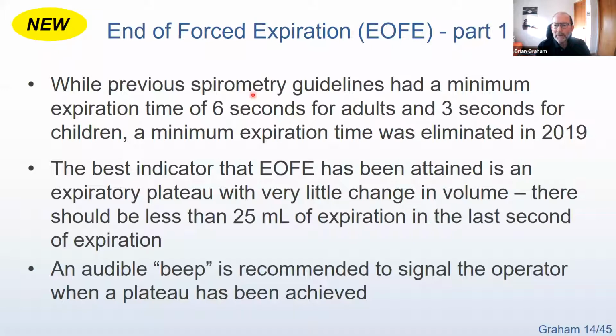So previous spirometry guidelines said you had a minimum expiration time of 6 seconds for adults, 3 seconds for children, and that's been eliminated in the new guidelines. We don't need that anymore. And there's good evidence to show that that's not required. So the best indicator that the end of forced expiration has been reached is the expiratory plateau, with less than 25 mLs of expiration in the last second of expiration.